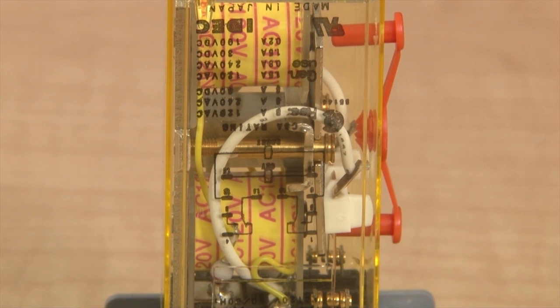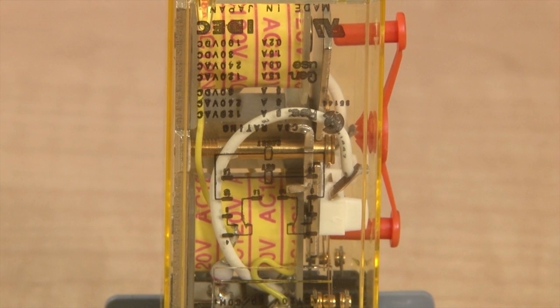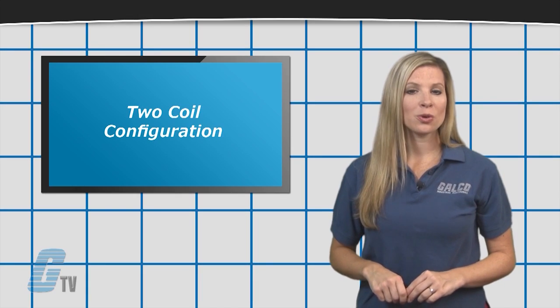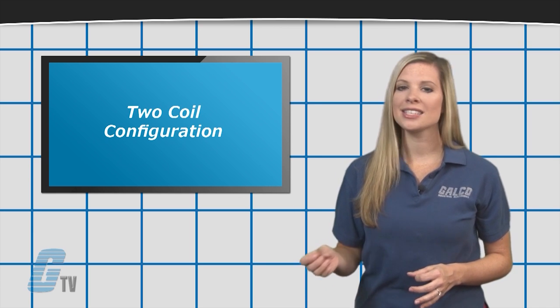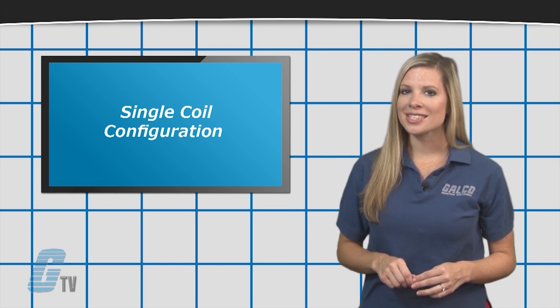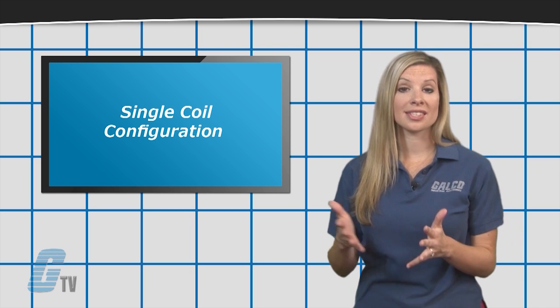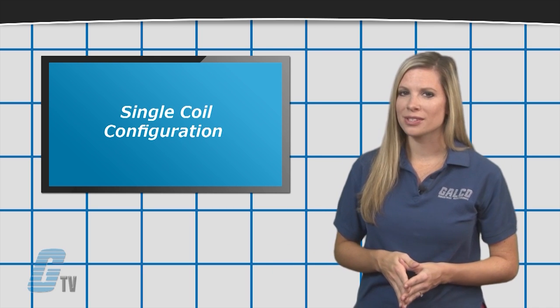It will stay in this direction until a redirected pulse moves the contact in the opposite direction. In the two coil configuration, this is done by each coil sending a different pulse, while in the single coil configuration this is accomplished when the polarity is reversed.